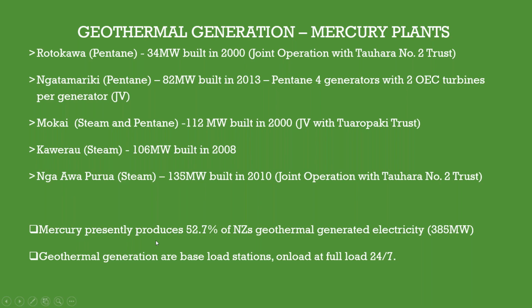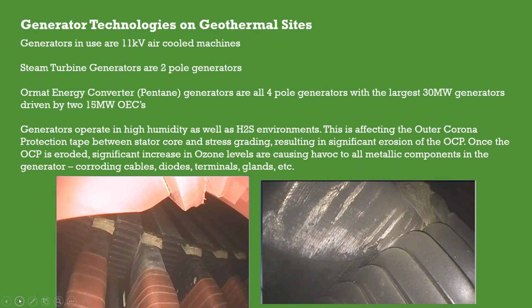Mercury presently produces 52.7% of New Zealand's geothermal generated electricity, which accounts for 385 megawatts. Geothermal generation stations are all baseload stations on load at full load 24/7. From a rotating machine point of view, I think that is what we like. We don't like these machines to go up and down all the time. So when we do a rotor inspection, everything just looks like new. There's no wear and tear to rotor insulation, or deformation of rotor coils, which is always really nice to see. But there are other issues. Nothing is always perfect.